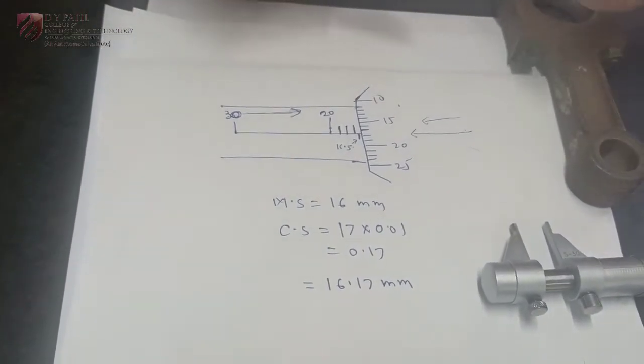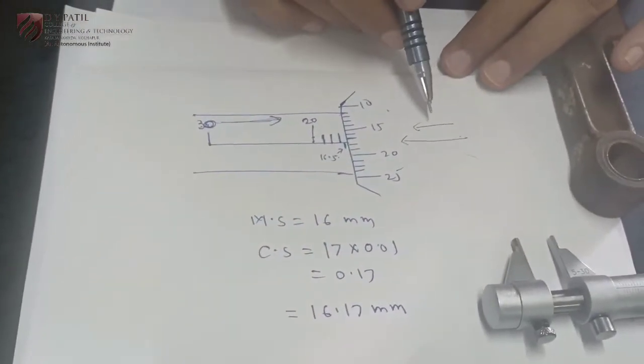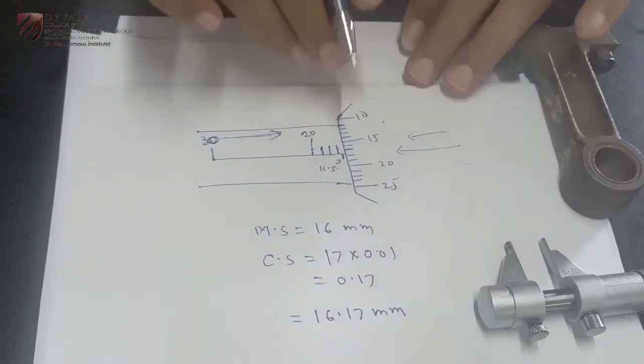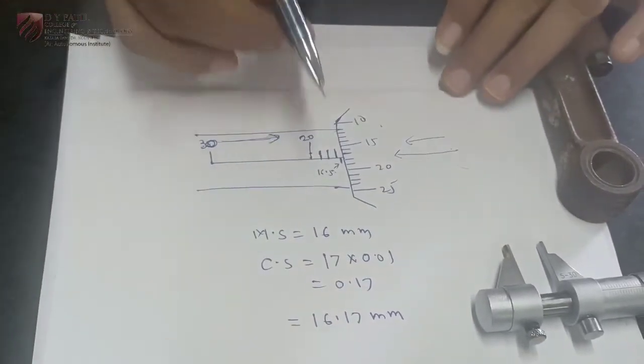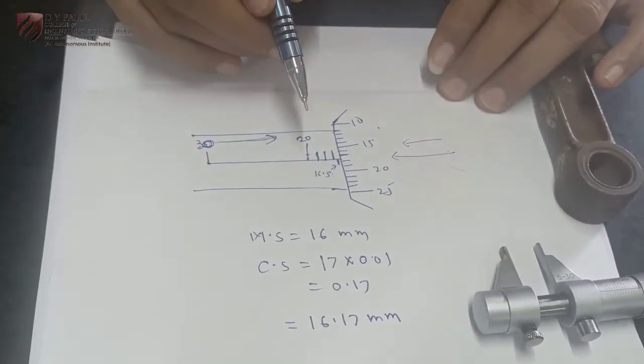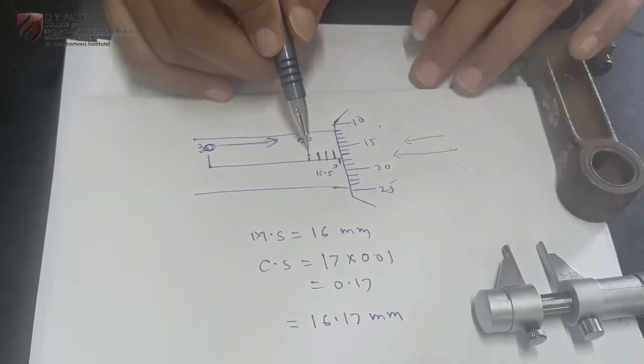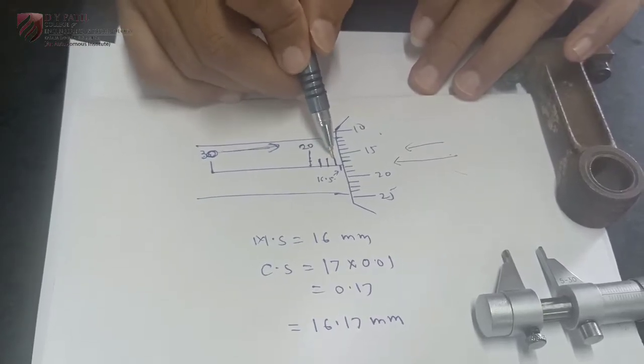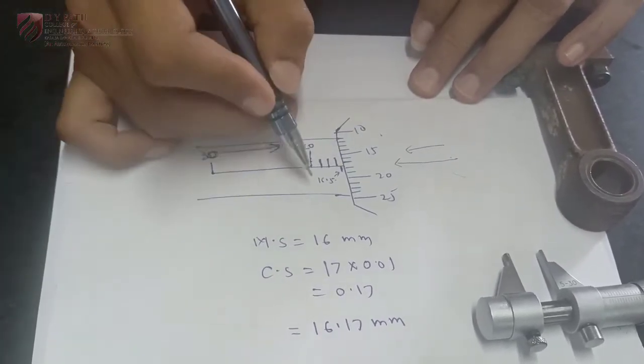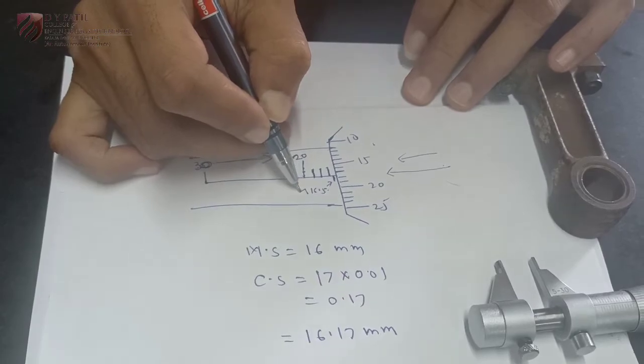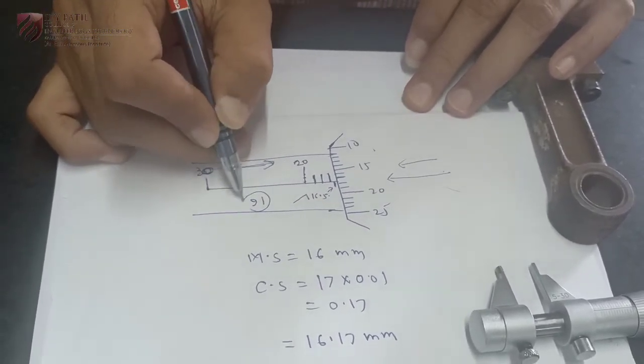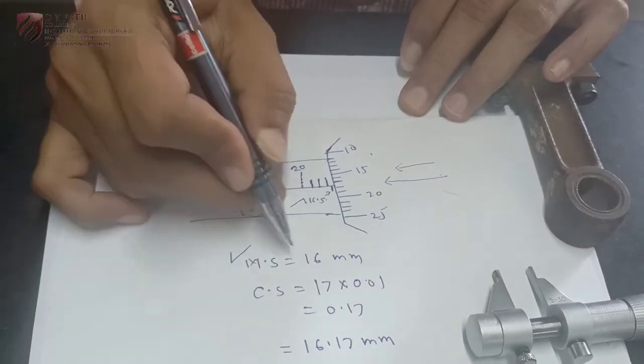When we rotate the thimble in clockwise direction, the thimble will start covering this reading. So you have to read that reading which has been covered. The reading which has been covered is actually not visible to you. For example in this particular case this is 20, 19, 18, 17 and this will be 16.5. So 16.5 is visible to me. That means division number 16 has been covered. That's why main scale reading is 16mm.